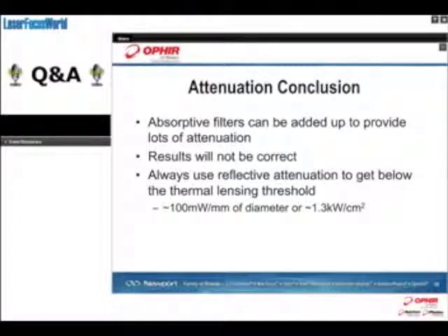And which approaches are used now to measure the very highest power beams? The spinning pinhole technique that I talked about, that PRIMES makes, really seems to be, for all intents and purposes, the leader in measuring caustic measurements of your multi-kilowatt beams.